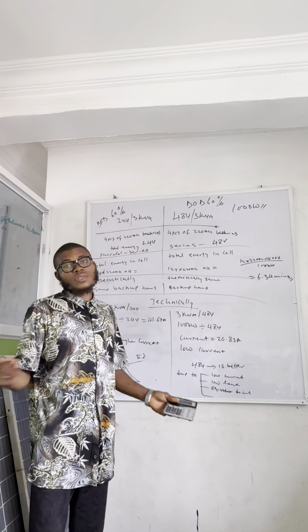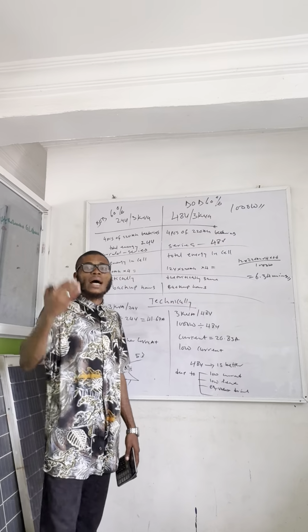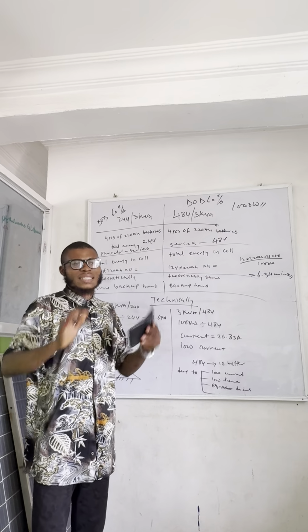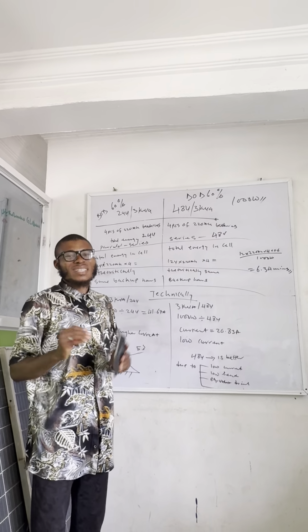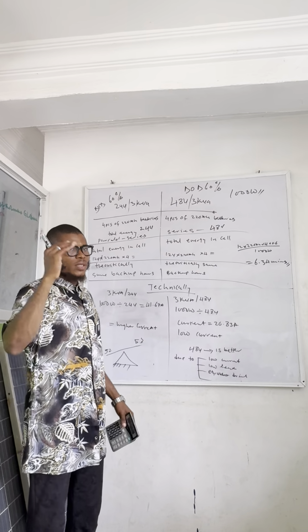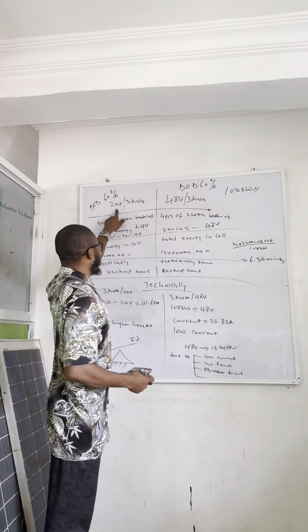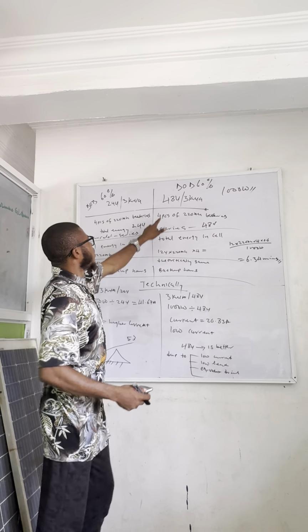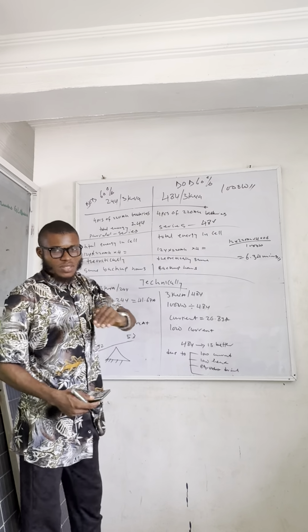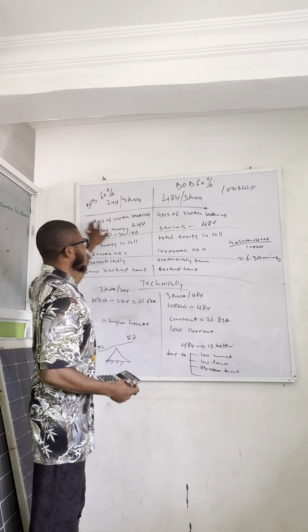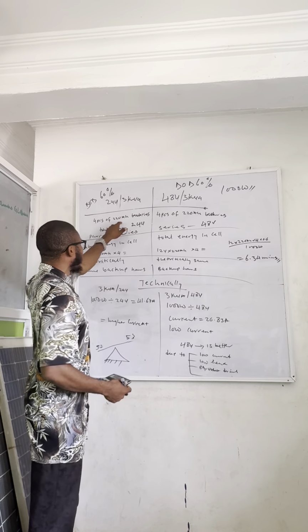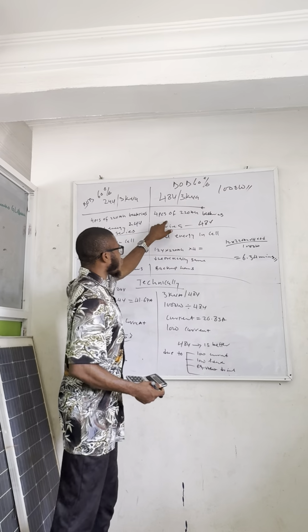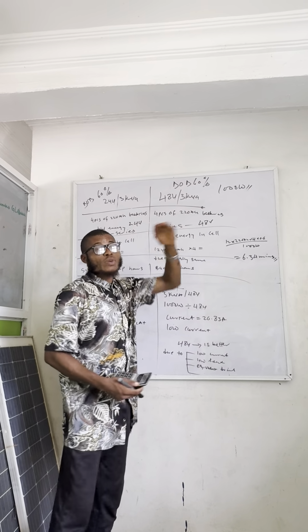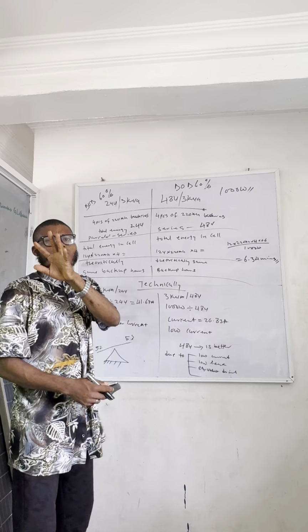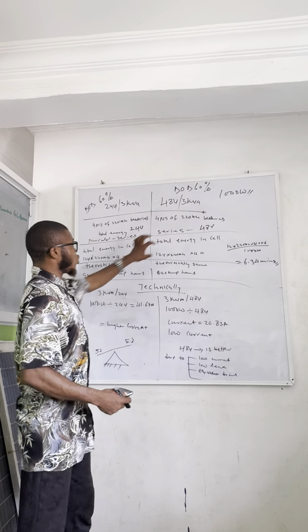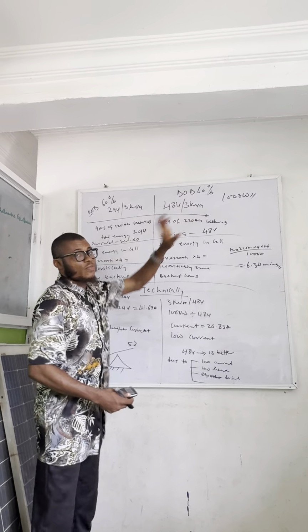In the absence of his reply, let me proceed and make an assumption, and let's assume that all the loads and everything requested are of the same capacity. Now let me break it down. The inverters involved are a 24 volt 3 kVA inverter and a 48 volt 3 kVA inverter from the same company, the same manufacturer, and each of them is going to be running with 4 pieces of 220 amp tubular battery. Now one thing you need to understand is this one has 4 batteries, this one also has 4. One is 24 volt, the other one is 48 volt.